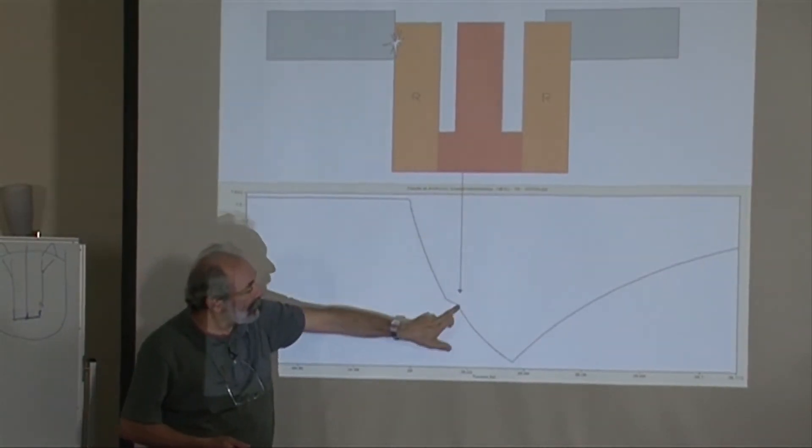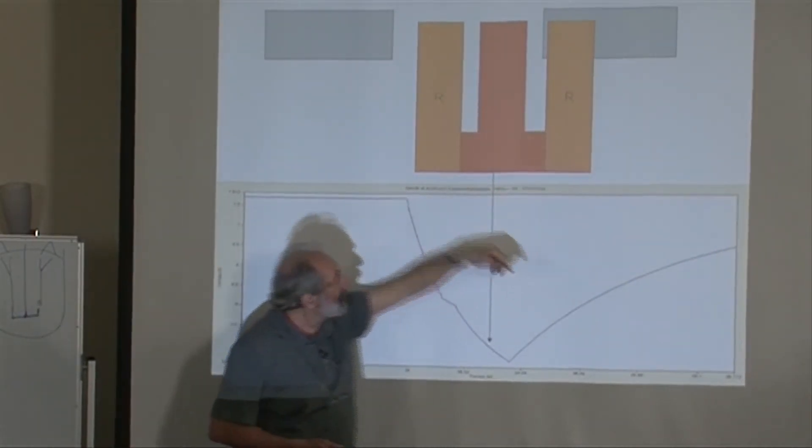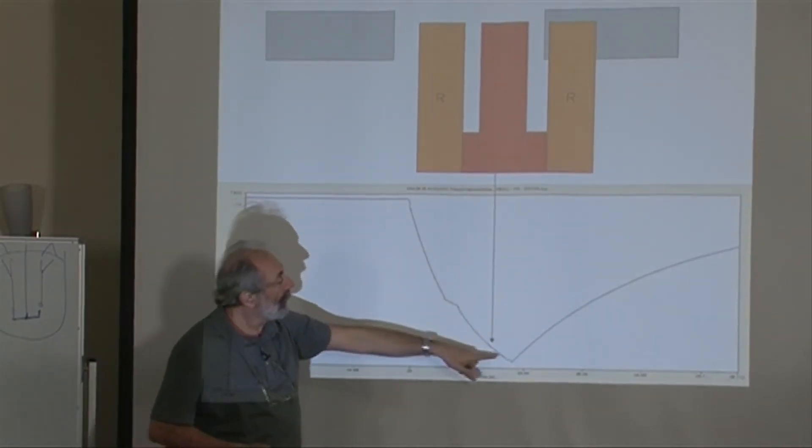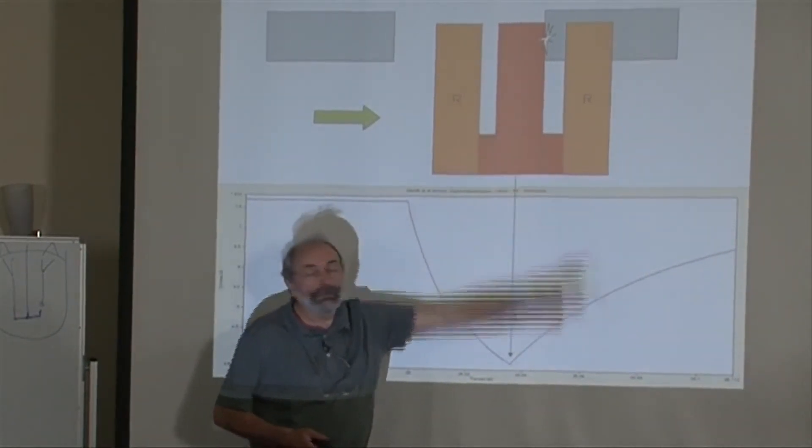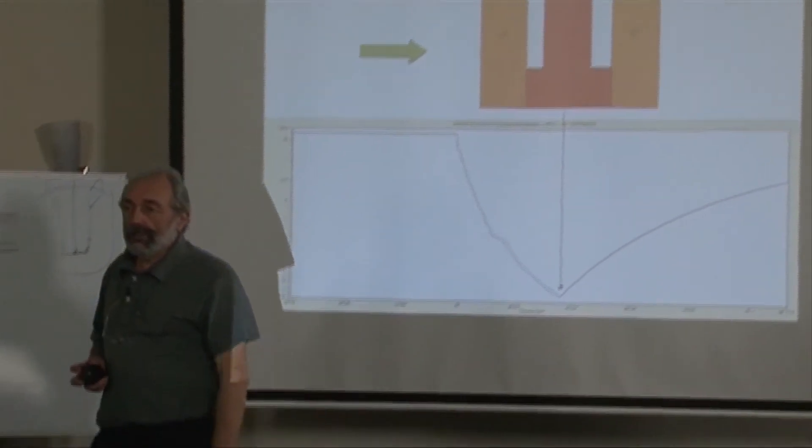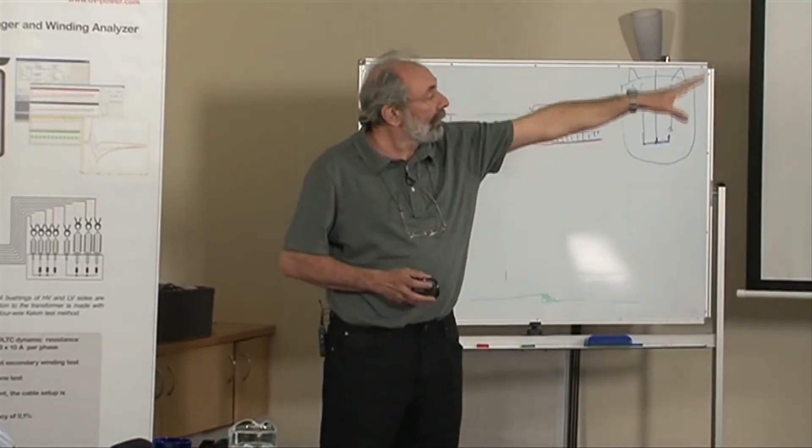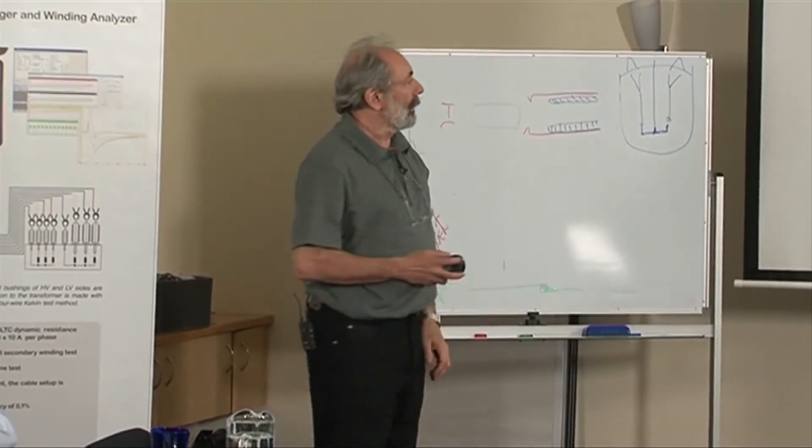When it separates, it continues going through only one resistor. So this is the same slope. Until the main contact makes with the next position. Now that it made, the current goes this exponential inductance type increase.